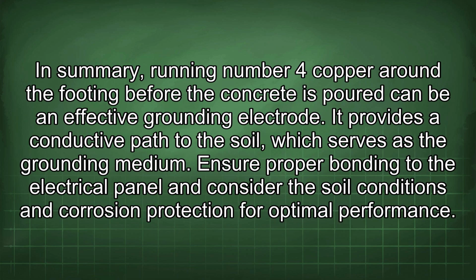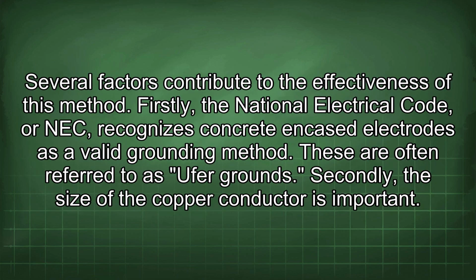In summary, running number 4 copper around the footing before the concrete is poured can be an effective grounding electrode. It provides a conductive path to the soil, which serves as the grounding medium. Ensure proper bonding to the electrical panel and consider the soil conditions and corrosion protection for optimal performance. Several factors contribute to the effectiveness of this method. Firstly, the National Electrical Code, or NEC, recognizes concrete encased electrodes as a valid grounding method. These are often referred to as UFER grounds.